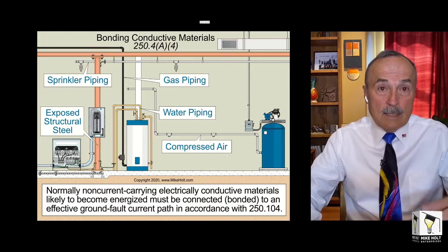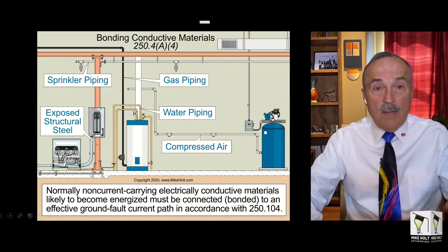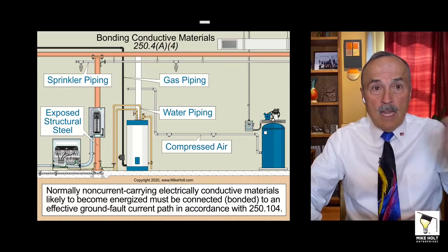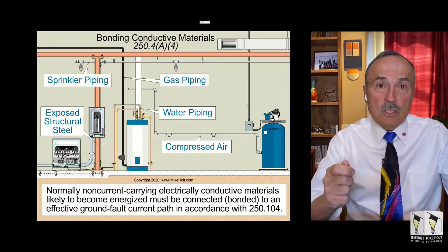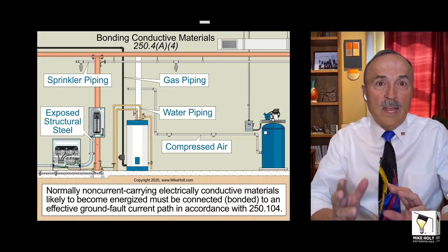Now, if you had a fireplace with a switch — turning on a fan or some other electrical component — then that gas piping connected to the fireplace would be likely to become energized. So the determination depends entirely on whether electrical conductors are present in proximity to the piping.